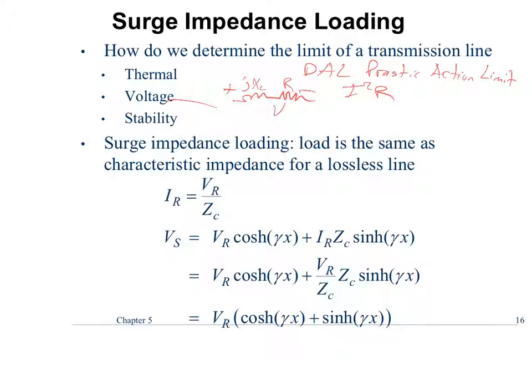So generally, the rule of thumb is if you're trying to exceed a plus or minus 10% across a line, that's the voltage stability limit. What is this stability limit that we're talking about here? What's stability? We've talked about it in this class. Is it you want a constant voltage at your load end? Well, that's not a stability limit. That's just a design criteria. We're going to try to keep the voltage at the customers fairly stable. It won't be perfect. It's plus or minus 3% usually at the customers, but we'll try to keep it stable.